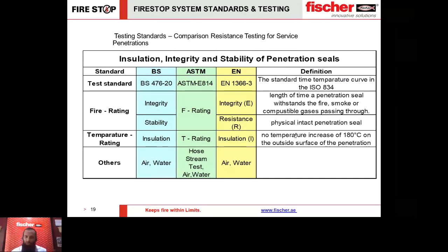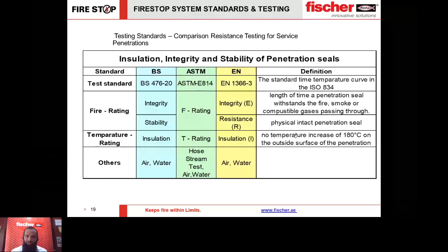During the initial phase of the project, plan the firewall and don't allow anybody to break it until you have planned what the solution will be. Based on the solution, give the cutout size. However, if somebody breaks the wall more than required and a parameter doesn't match — for example the listed system requires an annular gap of 45 mm but on site somebody has made a 60 mm annular gap — there is no listed system for that.